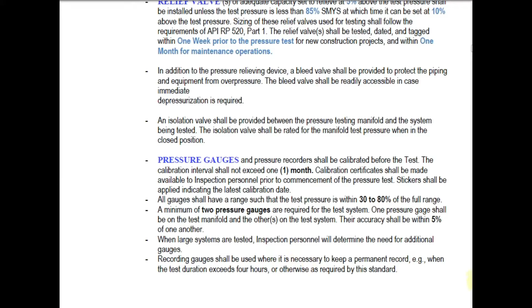A minimum of 2 pressure gauges are required for the test system. 1 pressure gauge shall be on the test manifold and the other on the test system. Their accuracy shall be within 5% of one another. When large systems are tested, inspection personnel will determine the need for additional gauges. Recording gauges shall be used where it is necessary to keep a permanent record, e.g., when the test duration exceeds 4 hours, or otherwise is required by this standard.